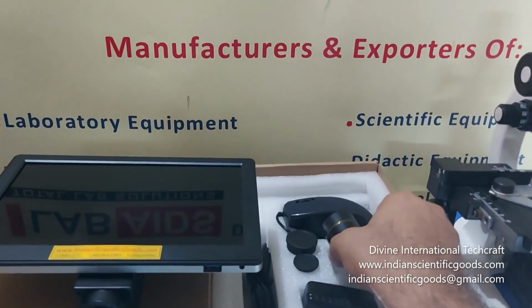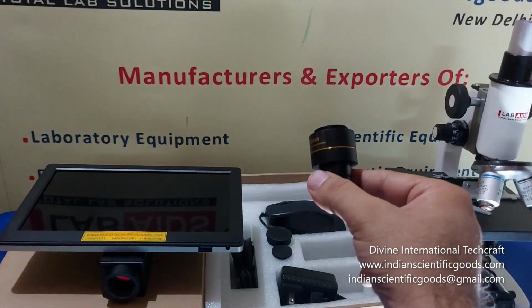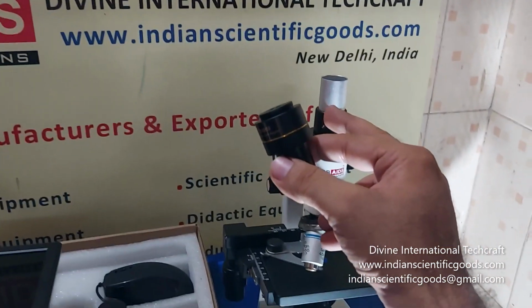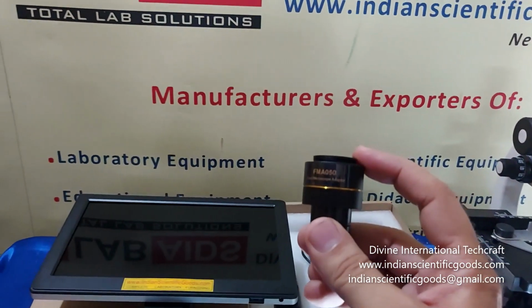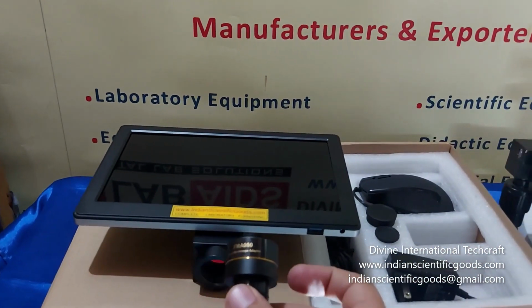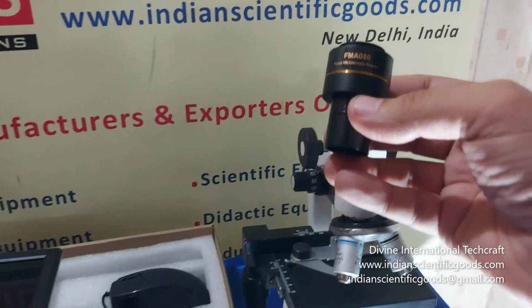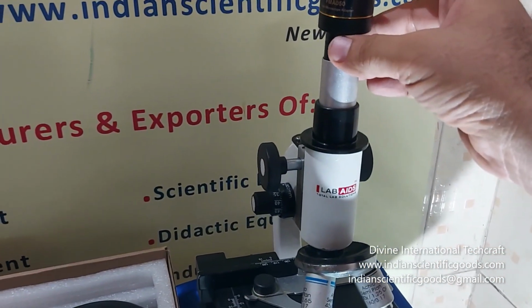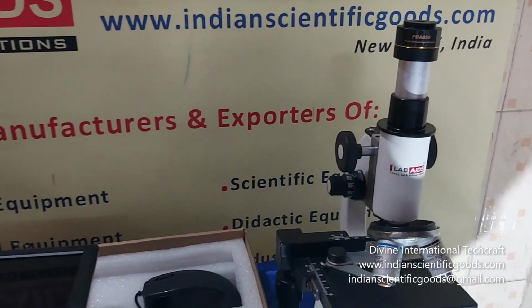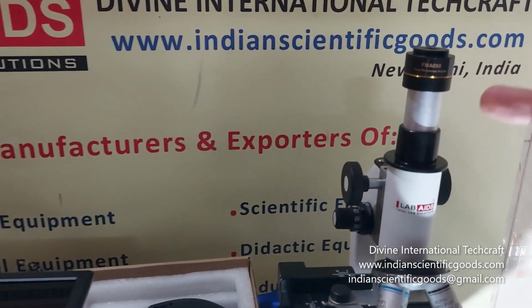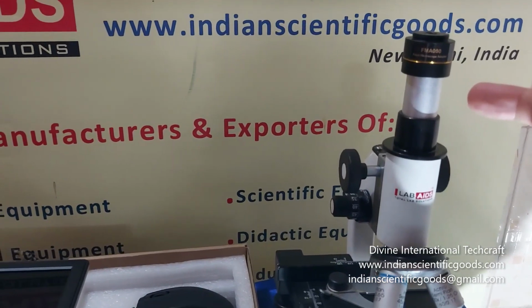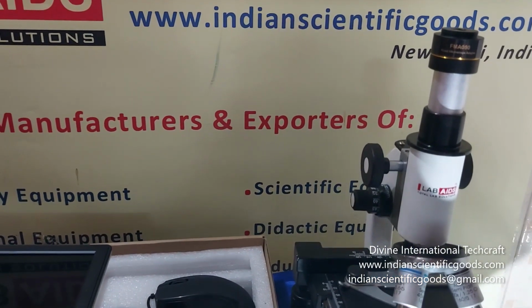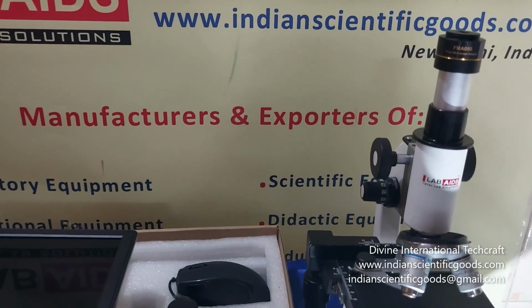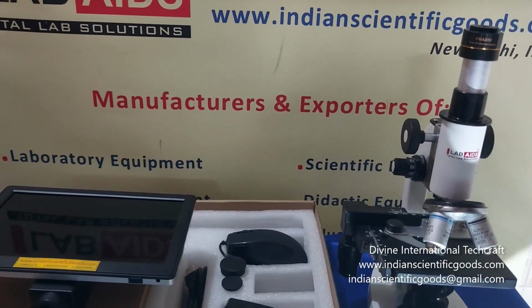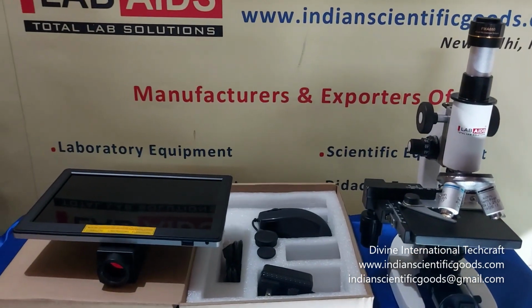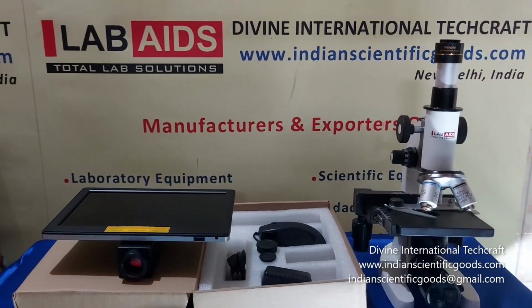This reduction lens is designed to couple C-mount cameras with a microscope's ocular tube or phototube. The male C-mount thread attaches to the camera and the 23 mm tube fits into any standard ocular tube with a 23 mm, 30 mm or 30.5 mm diameter. The 0.5x magnification is ideal for cameras with a 1/2 inch to 2/3 inch format sensor, optimizing the field of view and sensor coverage. It decreases magnification by half and doubles the field of view.